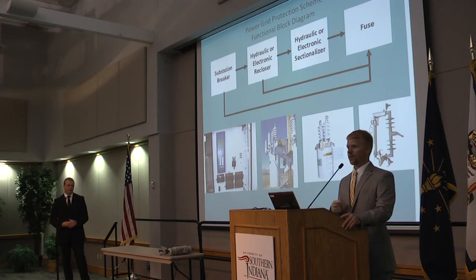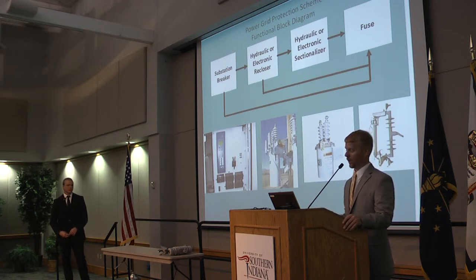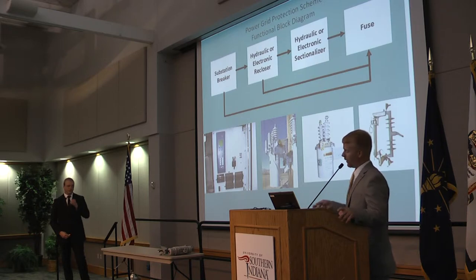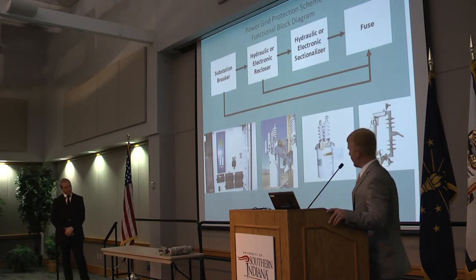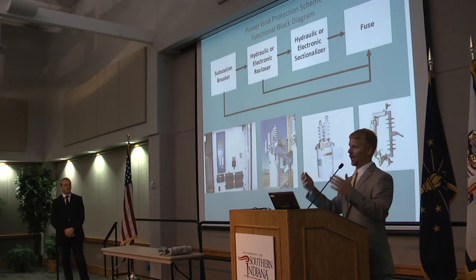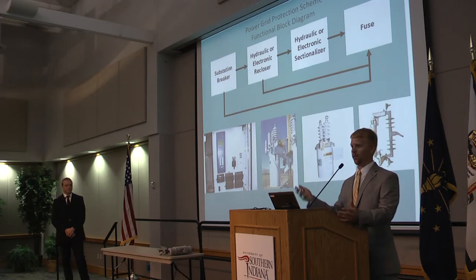The reasoning for this is if a branch or some wildlife is on the line, it will actually burn it off. So then the customers stay in power for as long as possible. The reason for the one fast curve is to possibly save the fuse. If we can save the fuse, then nobody has to go out and replace the fuse and everybody stays in power.